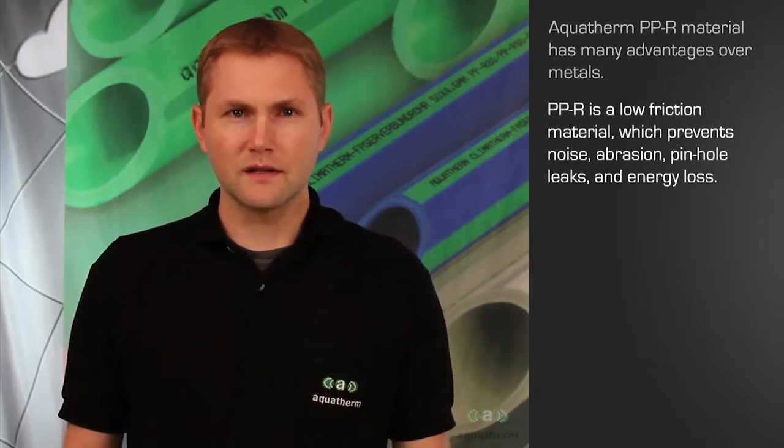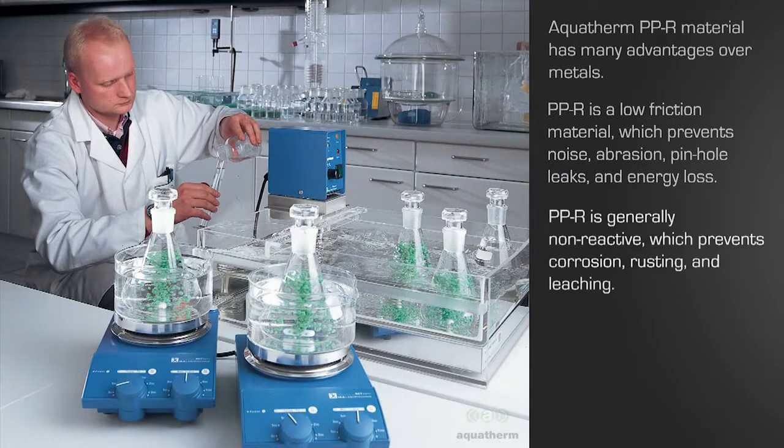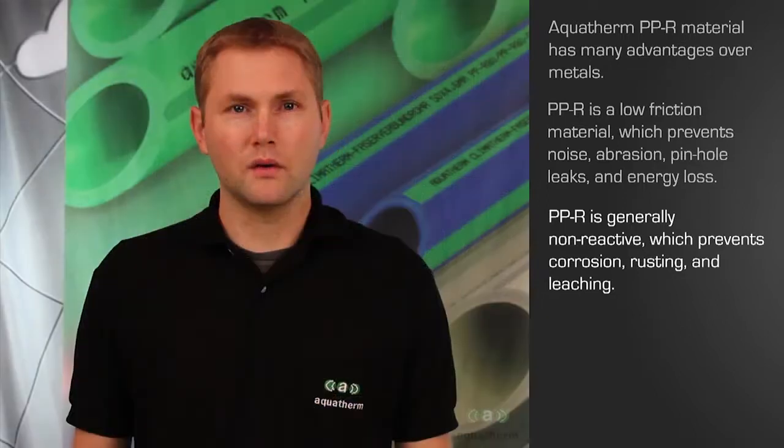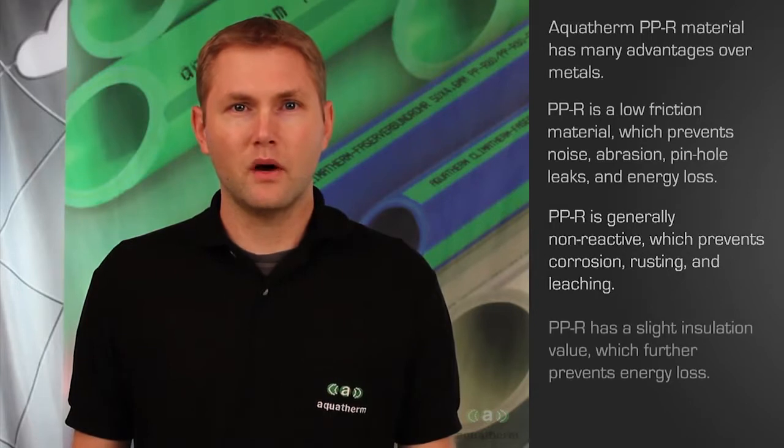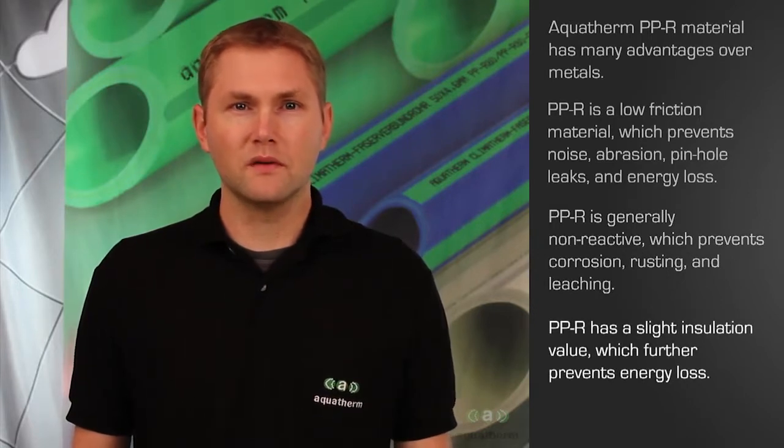Since polypropylene doesn't react with water, there is no corrosion or rusting, and no metallic taste. In many applications, polypropylene is outlasting metal pipe because of issues with water quality. Polypropylene also has a natural insulation value of about 1, which reduces the amount of additional insulation needed to meet energy codes.